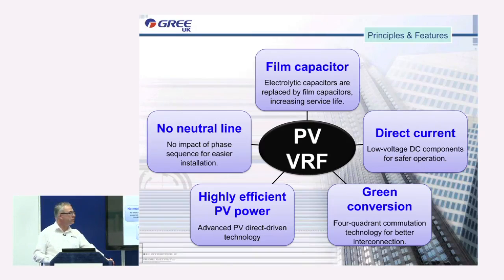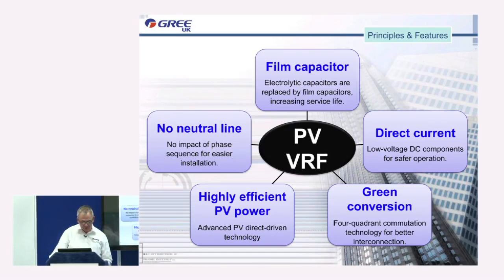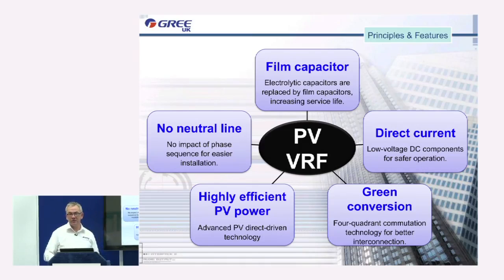So first of all, we use film capacitors instead of electrolytic capacitors. The main reason for using these is the advantages they give us, such as high voltage resistance, no polarity, and high impulse voltage endurance. They also have a much longer lifespan than electrolytic capacitors, which degrade over a much shorter period of time.